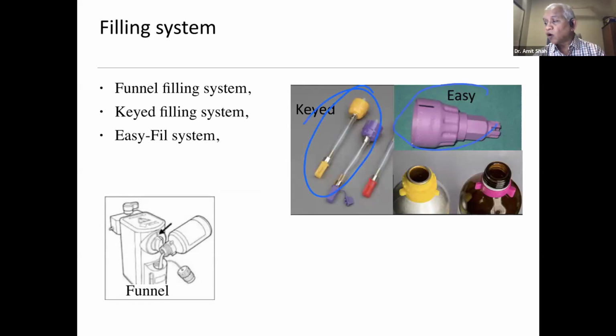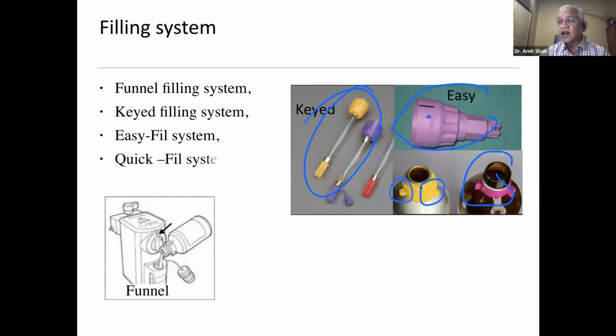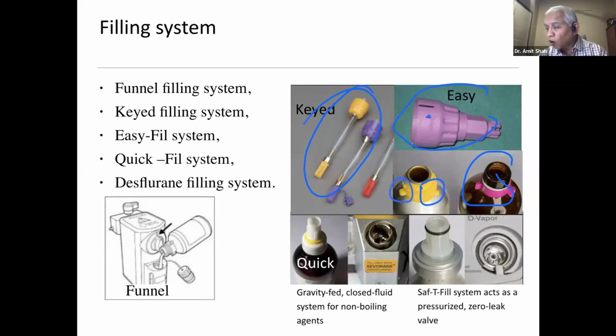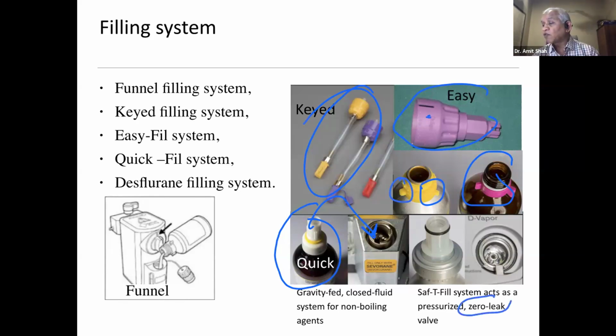Then came the easy filling, where you can fill it on the bottle, and the bottle will fill the appropriate cap only because of their arrangement on the neck of the bottle. So that was the easy. And then what we added was a quick filling system. Quick filling is a direct bottle which is now fitted onto the sevoflurane chamber opening, which is a gravity-fed closed-fill system for the sevoflurane. While for the desflurane, if you have used desflurane, it requires pressure and a very tight zero-leak valve. The reason is that the moment it comes in touch with the atmosphere, it immediately turns into vapor because of its very low boiling point. So it really requires a zero-leak type of system, which is there for the desflurane vaporizer filling system.